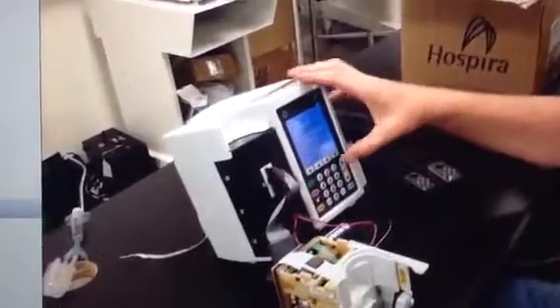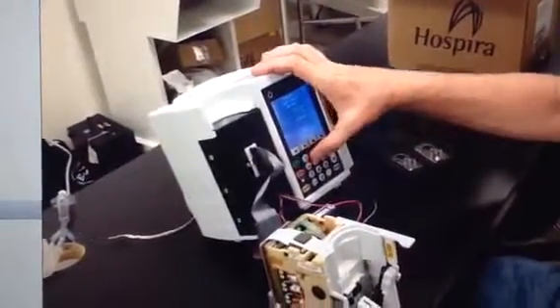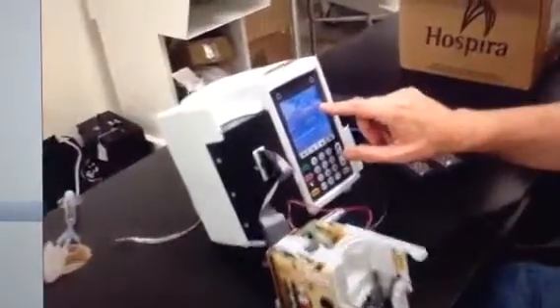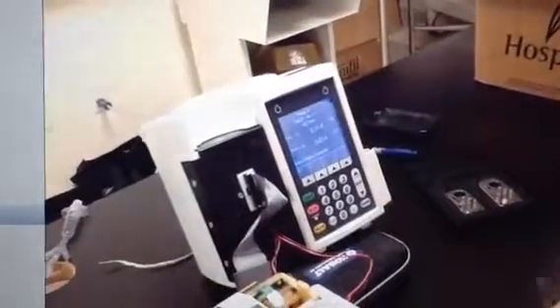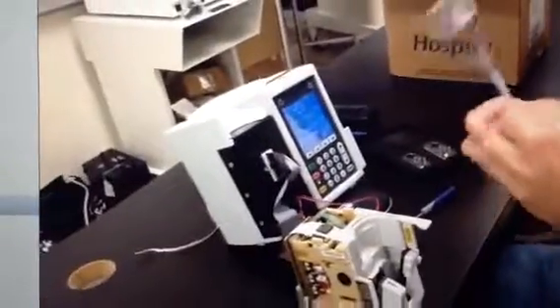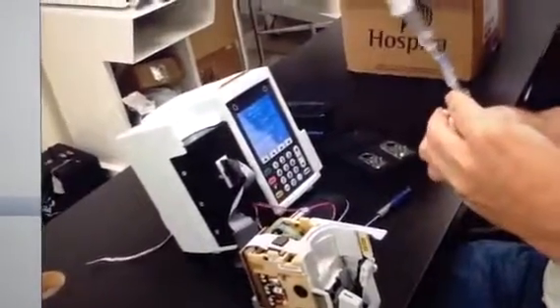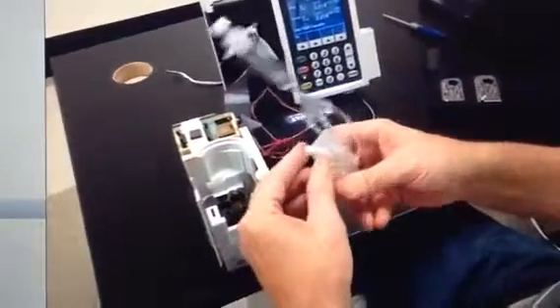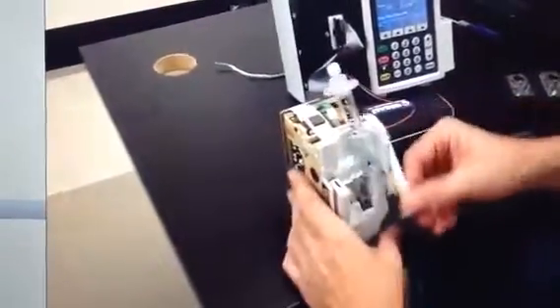Now to calibrate the air, we go to menu number 5, press start key to initiate test, empty cassette. This value needs to be below 0.097. If it's not, we need to replace this board. But that value is, so we hit set. And now we take a cassette filled with fluid, and I'm just going to pump the air out of it because it's laying on its side. Place the cassette in the door and close.